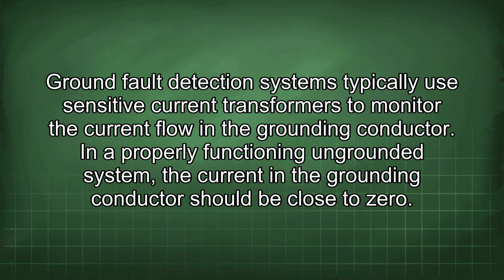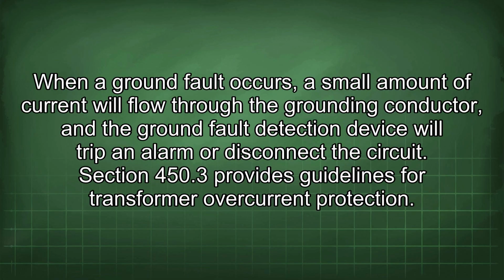Ground fault detection systems typically use sensitive current transformers to monitor the current flow in the grounding conductor. In a properly functioning ungrounded system, the current in the grounding conductor should be close to zero. When a ground fault occurs, a small amount of current will flow through the grounding conductor, and the ground fault detection device will trip an alarm or disconnect the circuit.